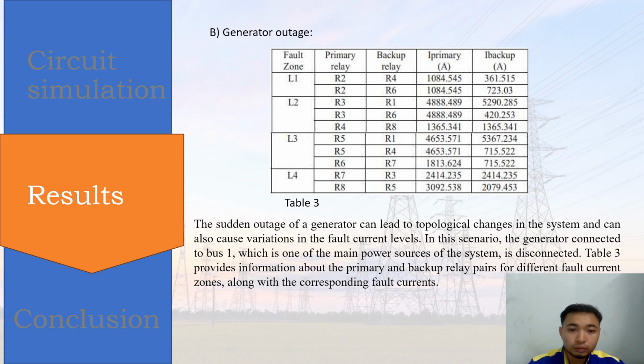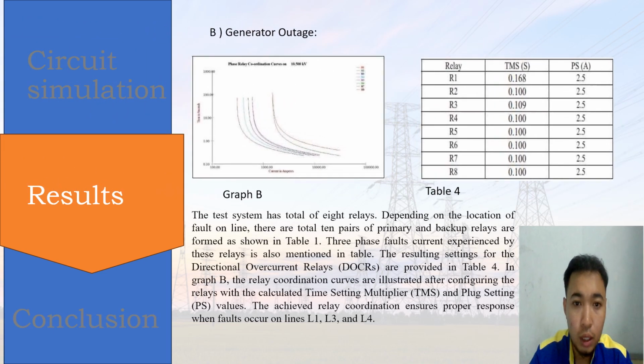So next, about the generator outage. There are two figures: graph B is the phase relay coordination curve, and on the right side is table 4, showing the resulting settings for the directional overcurrent relay. The test system has a total of 8 relays. Depending on the location of the fault on the line, there are a total of 10 pairs of primary and backup relays formed, as shown in table 1. The 3-phase fault current experienced by these relays is also mentioned in the table. The resulting settings for the directional overcurrent relay are provided in table 4.